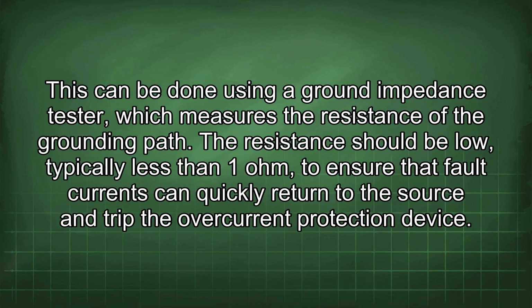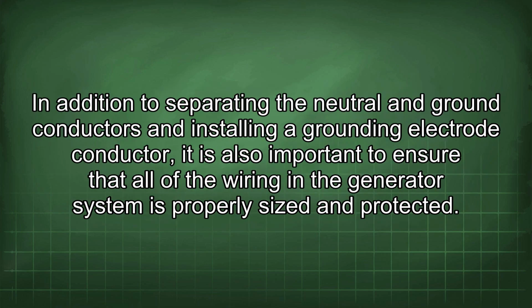This can be done using a ground impedance tester, which measures the resistance of the grounding path. The resistance should be low, typically less than 1 ohm, to ensure that fault currents can quickly return to the source and trip the overcurrent protection device. In addition to separating the neutral and ground conductors and installing a grounding electrode conductor, it is also important to ensure that all of the wiring in the generator system is properly sized and protected.